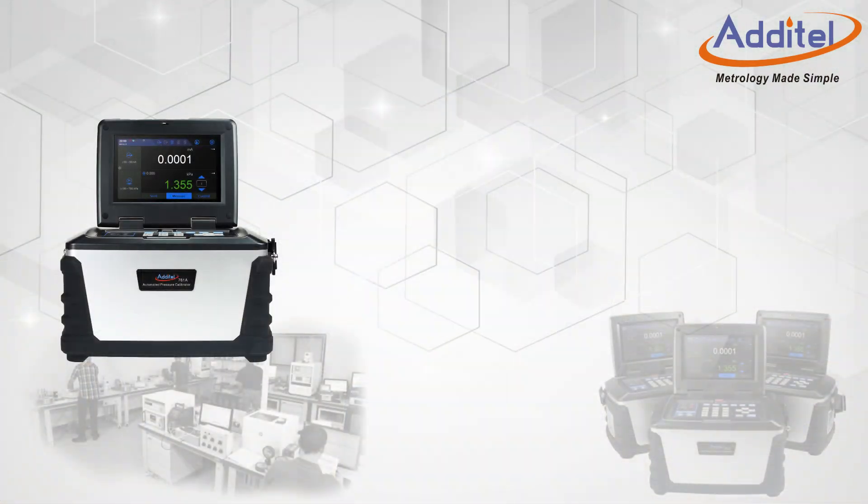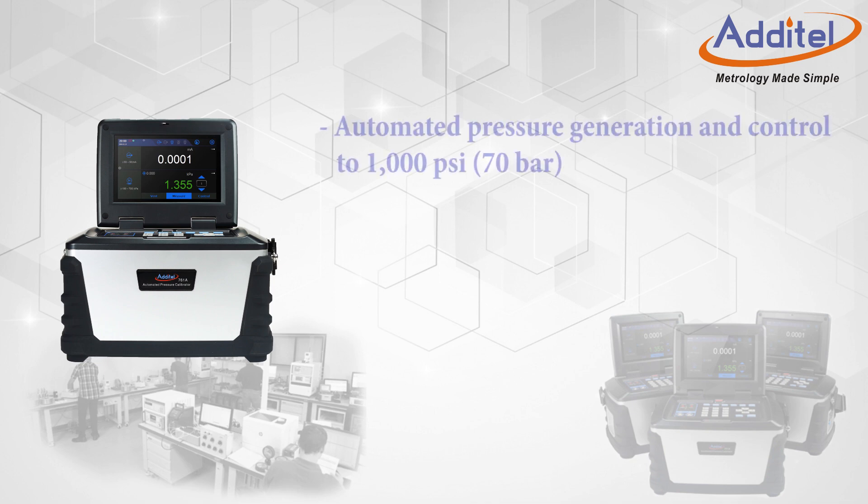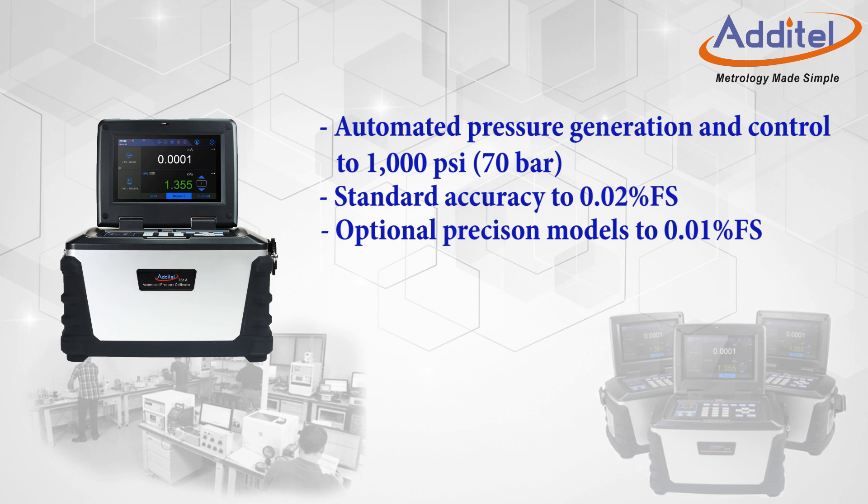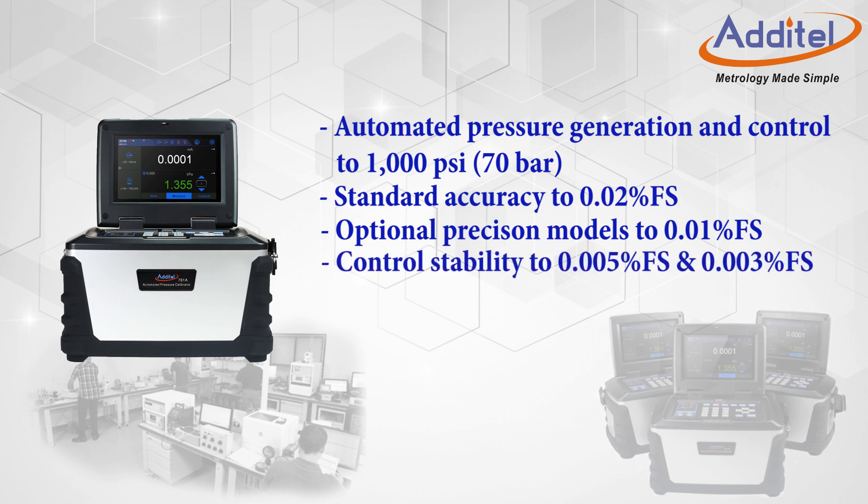Additel's 761A series of portable calibrators provides users with automated and self-contained pressure generation and control up to 1000 psi or 70 bar. 0.02% full-span accuracy as standard and an optional version to 0.01% full-span accuracy, with a control stability of 0.005% full-span and 0.003% full-span respectively.